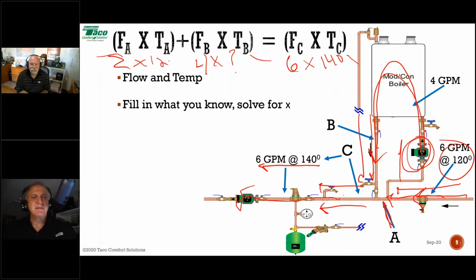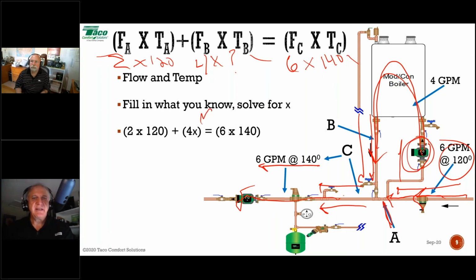Does that make sense? So by thinking logically and understanding that what goes into a T has to come out of a T, I've got this thing practically licked. I've got 5 of the 6 variables filled in. So I start out with 2 times 120 plus 4x equals 6 times 140. So 2 times 120 is 240. 4x is 4x. 6 times 140 is 840.